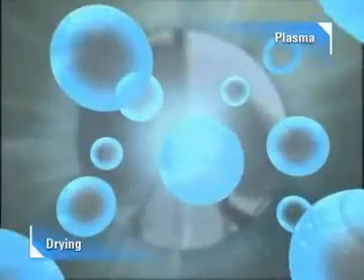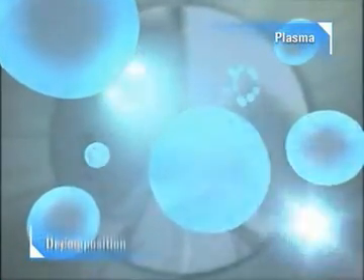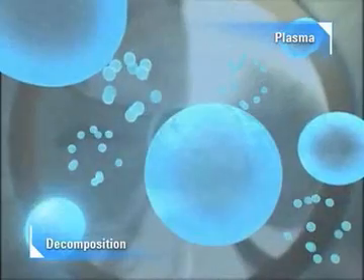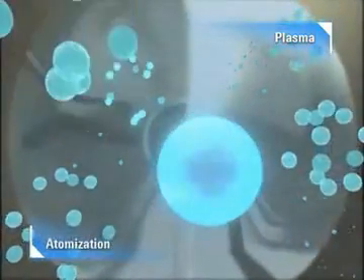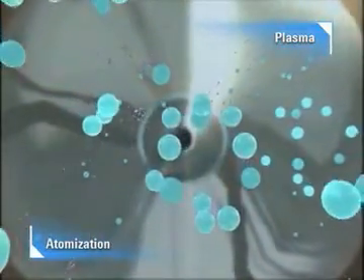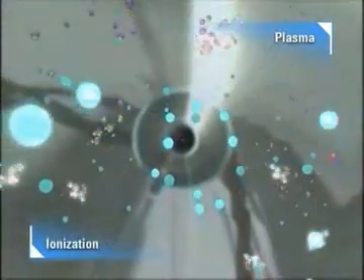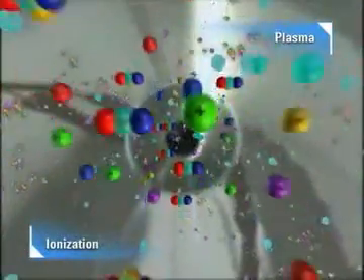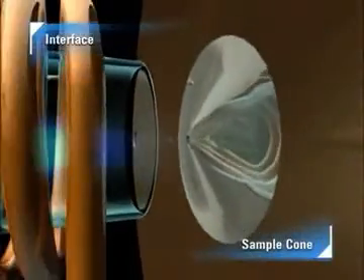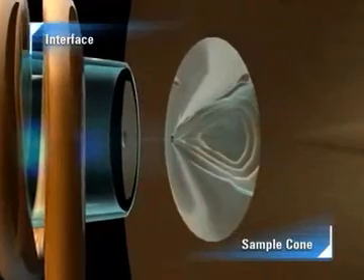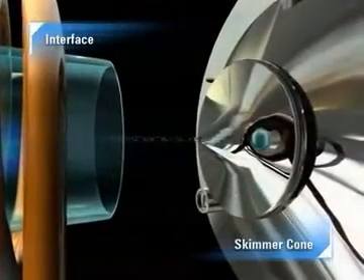As they travel through the high-temperature argon plasma, the aerosol droplets are dried, decomposed, atomized, and finally ionized, producing a rich source of positively charged ions. The ions are extracted from the plasma into the interface through the sampling orifice, and then through the skimmer cone into the high-vacuum region containing the ion lenses and mass analyzer.